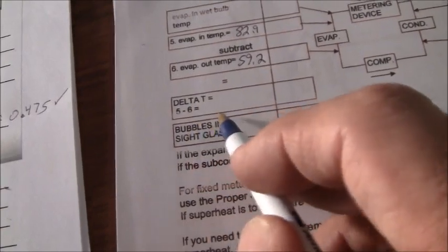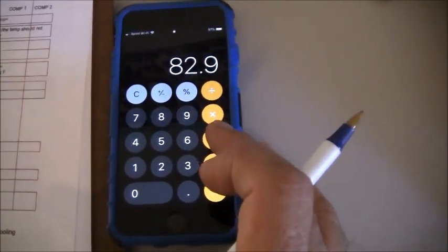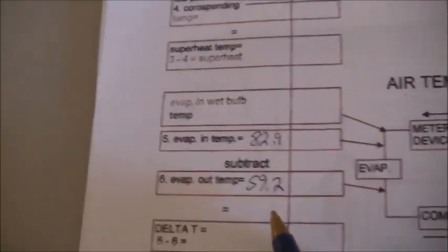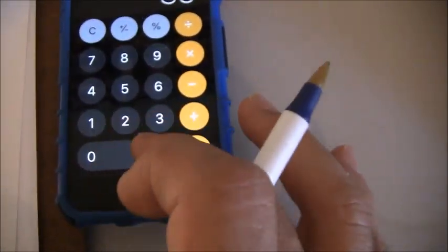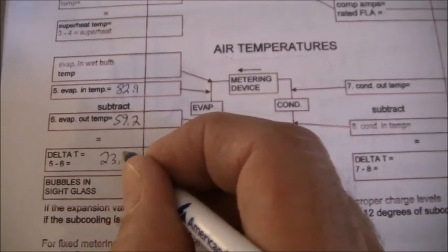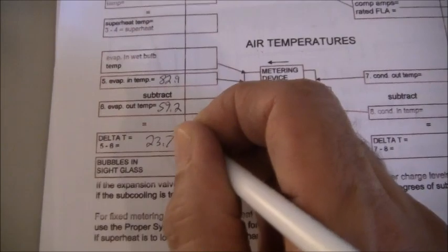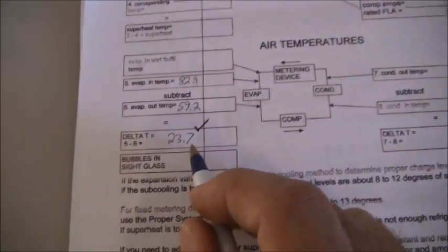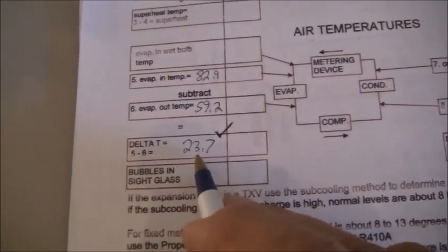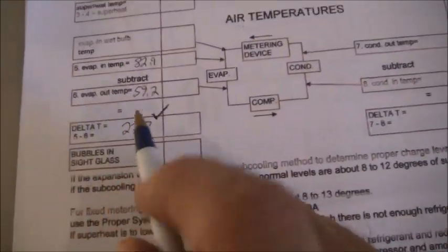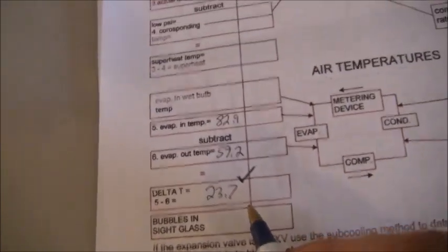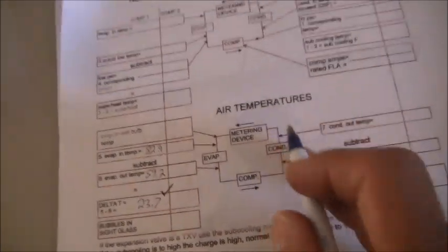We write that number down right here, 59.2. And then we take 5 minus 6, that will give us our delta T. Okay, so 5 is 82.9. We're going to subtract from that 59.2 because that is the supply temperature. That's going to give us a delta T of 23.7. That goes right here, 23.7. Is that good? Yes. That is telling you that the evap coil is giving you a greater than 20 degree split. As far as airflows go and stuff like that, that is pretty good. So we don't have an issue with anything on the inside. As a matter of fact, we really don't even need to put gauges on here. But let's go ahead. Well, definitely let's go outside and let's get our air temperatures, and then we'll go from there.